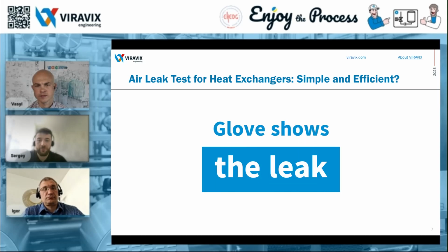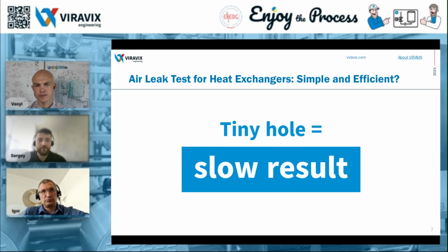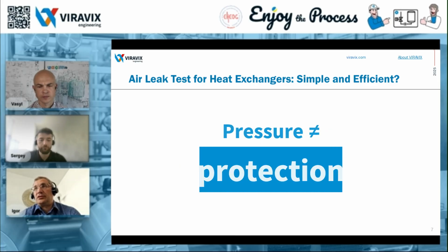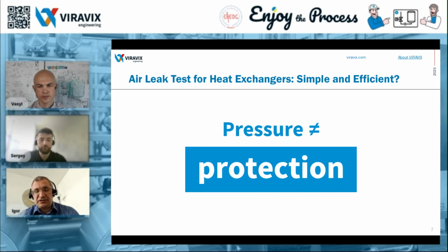Visual inspection is carried out by observing whether the latex glove inflates, indicating the presence of air leakage. If there's a small hole, the glove inflates very slowly. If there's always excess pressure on the product side, then in the event of a leak, we'd constantly be contaminating the heat transfer medium.